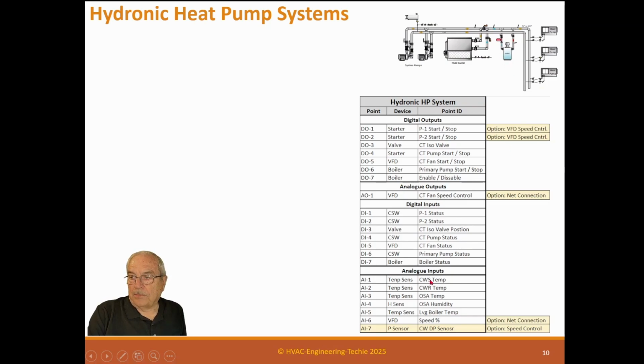Analog inputs are a temperature sensor for condenser water supply, a temperature sensor for condenser water return, outside air temperature and outside humidity again, and then a temperature sensor for the leaving boiler temperature. So we have a temperature sensor up here just for the leaving boiler temperature. And we have a VFD speed percentage to know what speed our cooling tower is running. And then if we want this variable flow again, we go over here and put valves and then put VFDs here, and then we'd have to put a pressure sensor just like the other one if we wanted variable speed. We could do that by putting these valves out here. Same thing as the other. And then these are optional points. If we have variable speed, we want VFDs on those. We can put a net connection on this VFD, and then we can net connection all the VFDs.